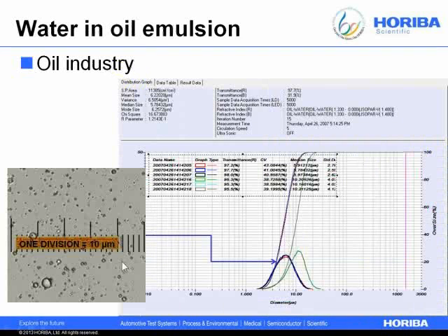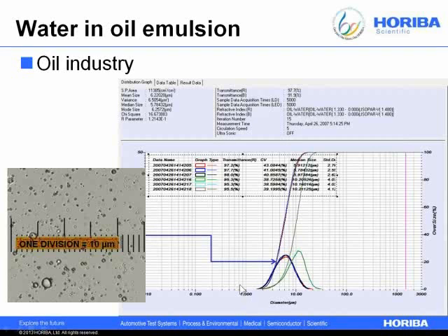An example measurement from a water-and-oil emulsion from the oil industry shows a micrograph with droplets around 5 microns — each division is 10 microns. The size distribution obtained by laser diffraction shows three repeats of each of two samples, overlaying quite nicely. The micrograph matches the diffraction result, with a peak around 5 microns and a tail past 10 microns. A second pharma emulsion shows a bimodal distribution using a fraction cell for small sample volume — the glass cell is chemically resistant, which is useful when your continuous phase is oil.